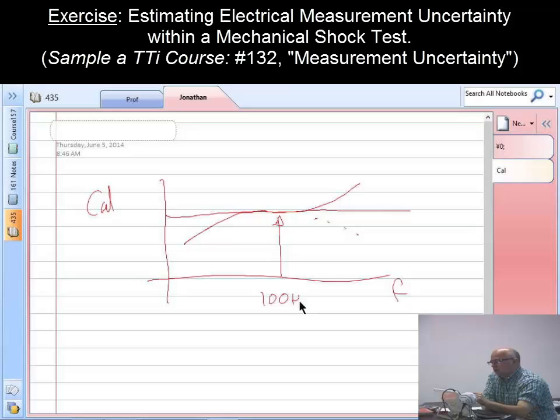Yes. A lot of them are targeted to 1 kilohertz. And basically it's a one-point calibration. At that frequency, that's it. And within your range of 20 to 2 kilohertz, I'm showing that one there, but I don't know what your exact one is. Here you can be a few dB off, and it's still considered to be a calibrated transducer.